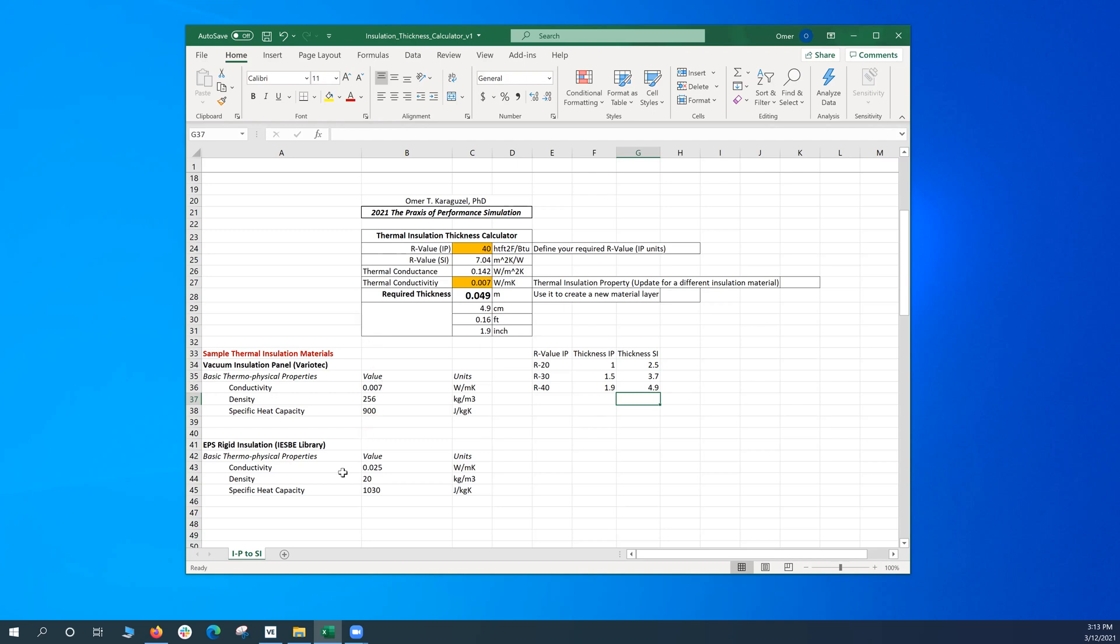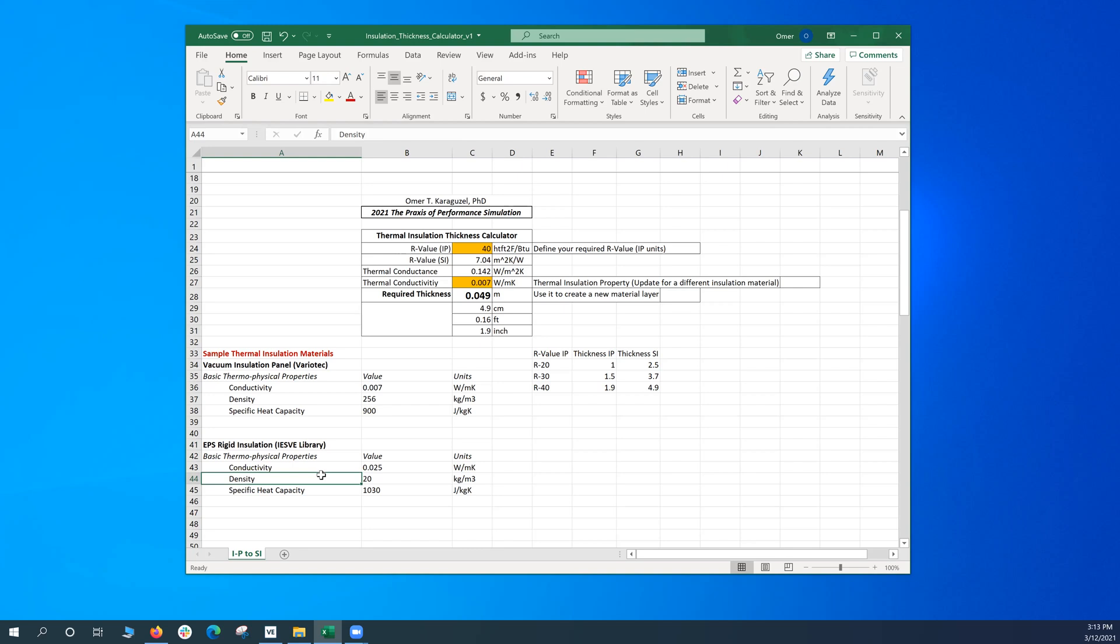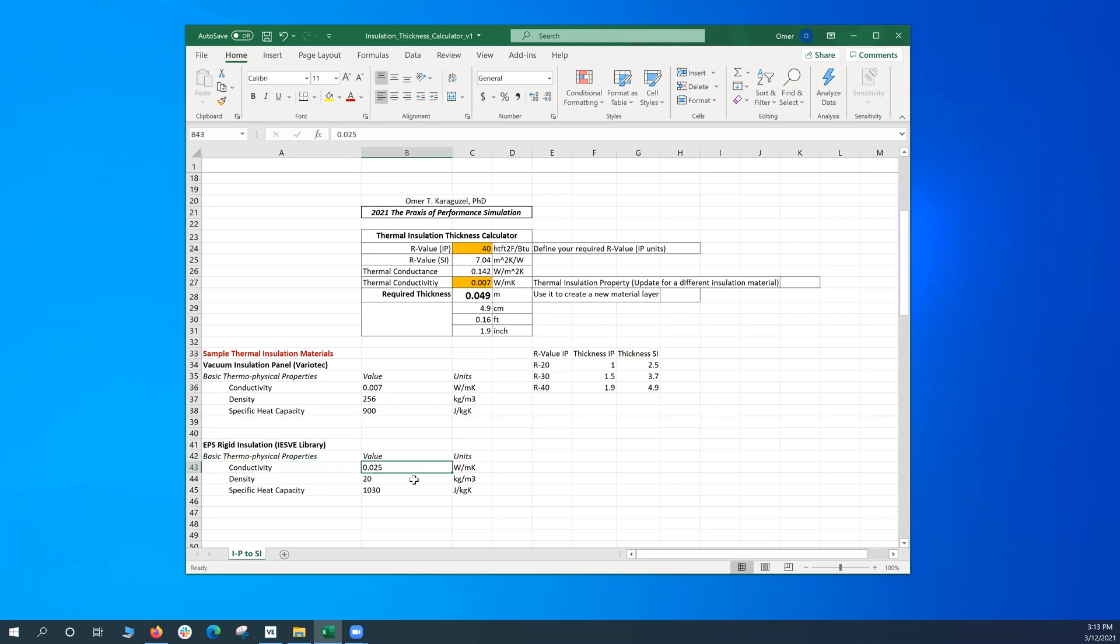Let's try a different type of thermal insulation, like EPS rigid insulation panel that I derived from the IES-VE library. Just we conducted something along the way. And here this material has a thermal conductivity of 0.025 watts per meter Kelvin. Let's plug in the number, but pay attention to the thickness. Let's keep an eye on the required thickness. With the vacuum insulation, the thickness is about 4.9 centimeters. Let's see what will happen to the thickness with the EPS rigid.